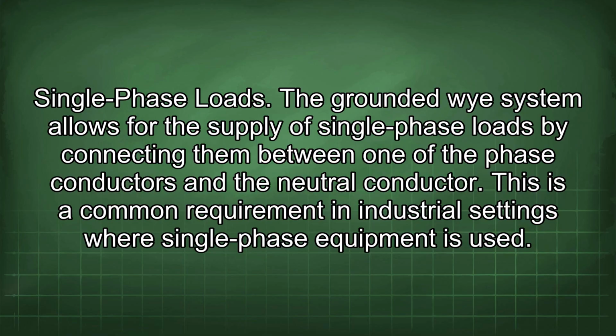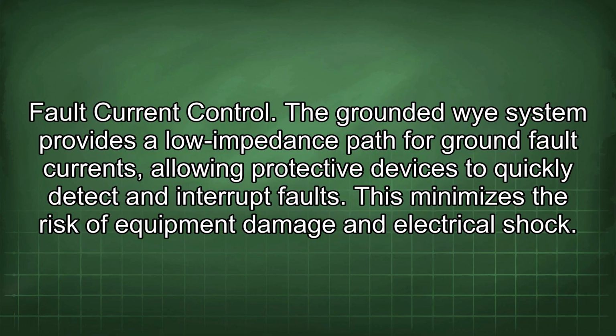This is a common requirement in industrial settings where single-phase equipment is used. Fault current control. The grounded Y system provides a low impedance path for ground fault currents, allowing protective devices to quickly detect and interrupt faults. This minimizes the risk of equipment damage and electrical shock.